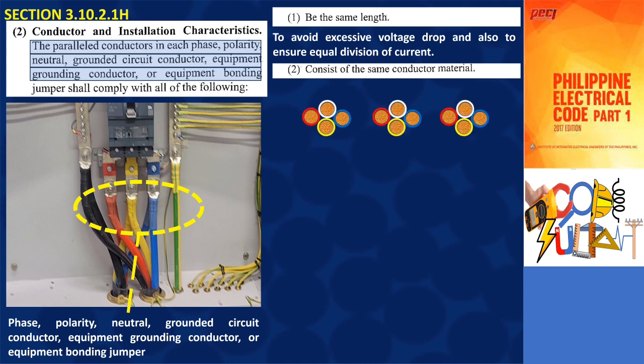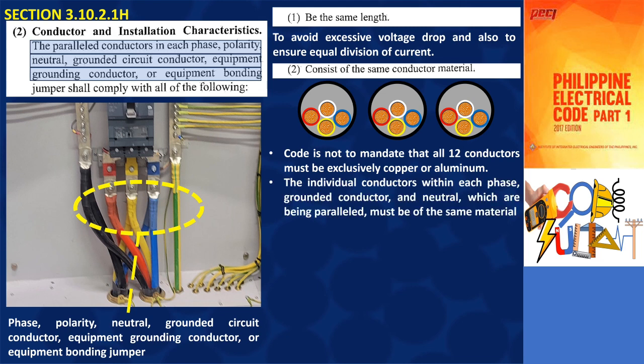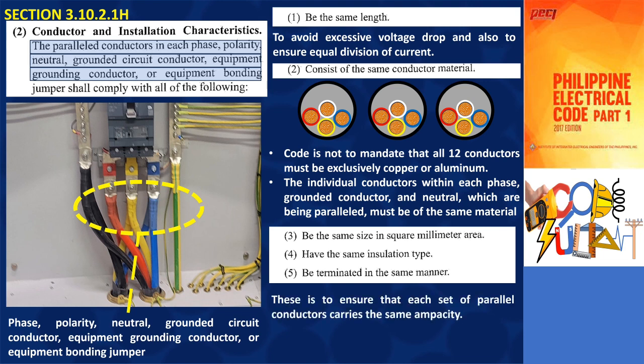To illustrate this, let's consider an example where 12 conductors are being paralleled for a three-phase, four-wire, 400Y/230V AC circuit. In this scenario, it is permissible to install four conductors in each of the three raceways. It's important to note that the code does not mandate that all 12 conductors must be exclusively copper or aluminum. However, the code does emphasize that the individual conductors within each phase, grounded conductor, and neutral which are being paralleled must be of the same material, the same square millimeters area, insulation type, and be terminated in the same manner. Following all these rules ensures that each set of parallel conductors carries the same ampacity.